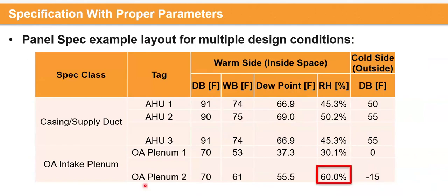One thing we did note on this spec is for the most extreme case, which would be in the winter, we did see that they're specifying a 60% relative humidity within the warm space or the conditioned space, which is very, very high. Based on research and recommendations out there, relative humidity would be within 30 to 35% in the winter and just at maximum 50% in the summer. So we would default this back to 35% within the recommended limits just to test if our panels would work in a typical real world scenario.